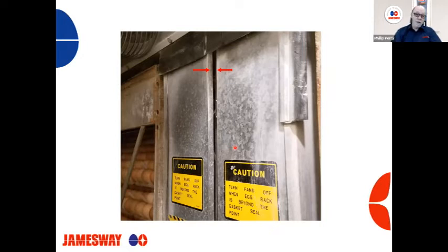And this is a big thing here. Over time, they become bent. A lot of times they can be bent back in place to make sure that you get a good seal. I have seen some foam gasket material put in here if they were beyond repair, and that was a good solution to keep that air moving back through the eggs properly.